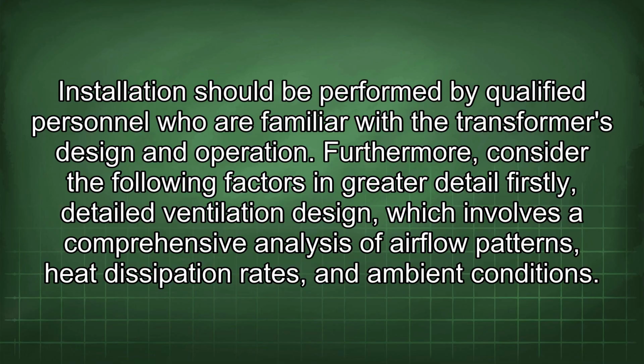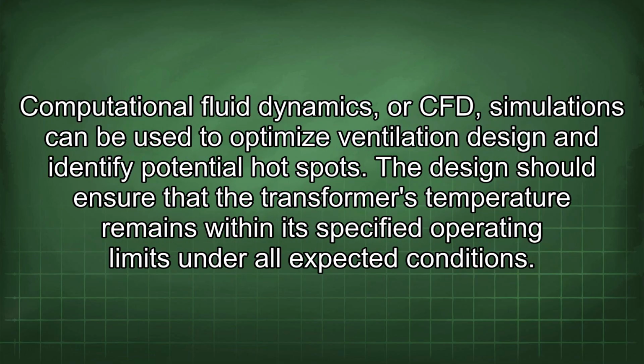Firstly, detailed ventilation design, which involves a comprehensive analysis of airflow patterns, heat dissipation rates, and ambient conditions. Computational fluid dynamics, or CFD, simulations can be used to optimize ventilation design and identify potential hotspots. The design should ensure that the transformer's temperature remains within its specified operating limits under all expected conditions.